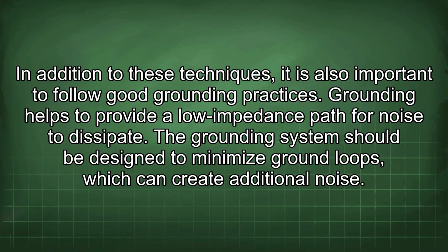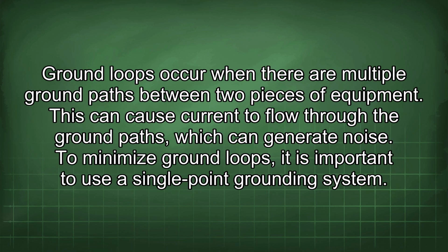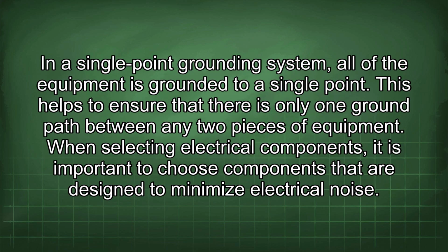Grounding helps to provide a low impedance path for noise to dissipate. The grounding system should be designed to minimize ground loops, which can create additional noise. Ground loops occur when there are multiple ground paths between two pieces of equipment. This can cause current to flow through the ground paths, which can generate noise. To minimize ground loops, it is important to use a single-point grounding system. In a single-point grounding system, all of the equipment is grounded to a single point. This helps to ensure that there is only one ground path between any two pieces of equipment.